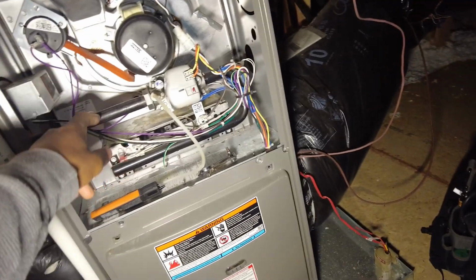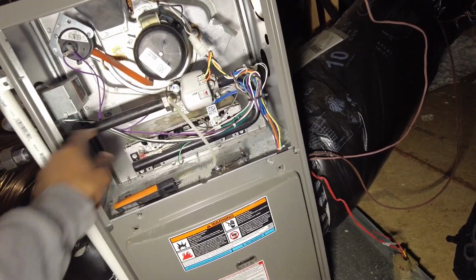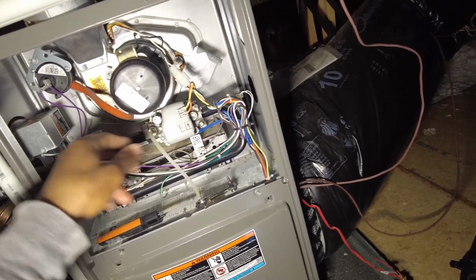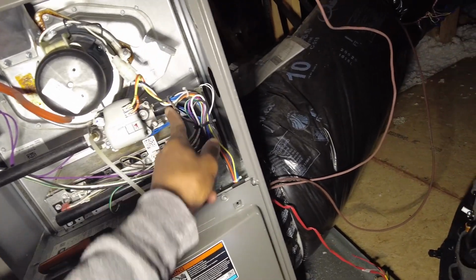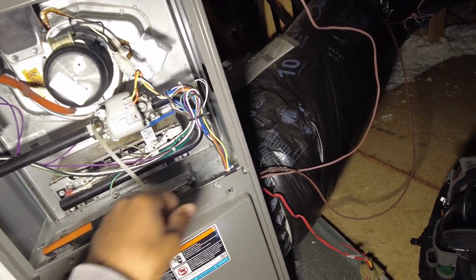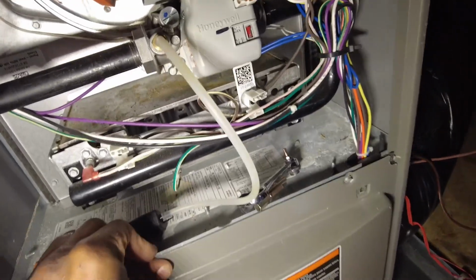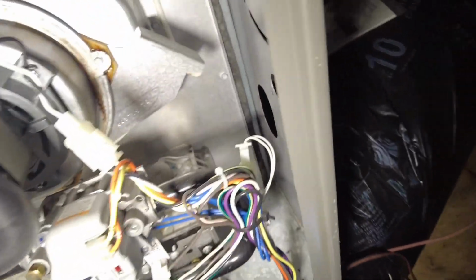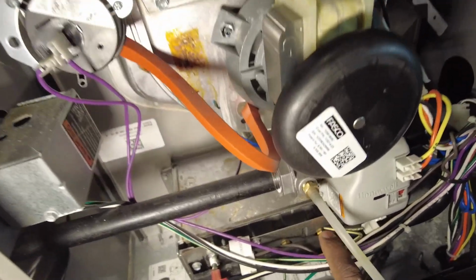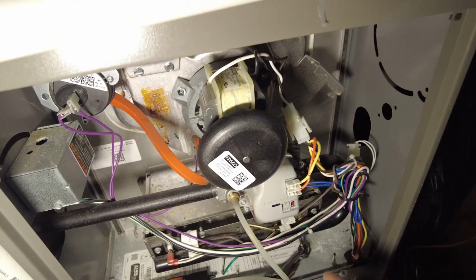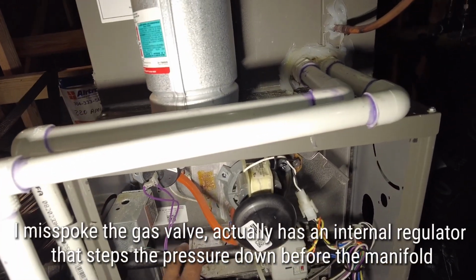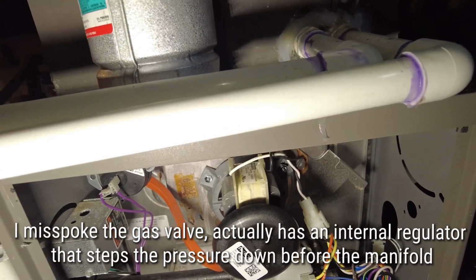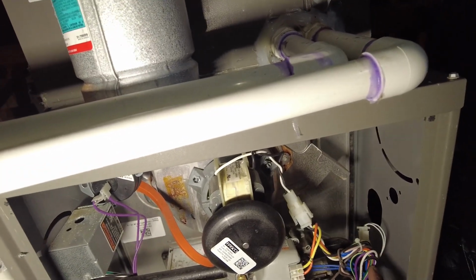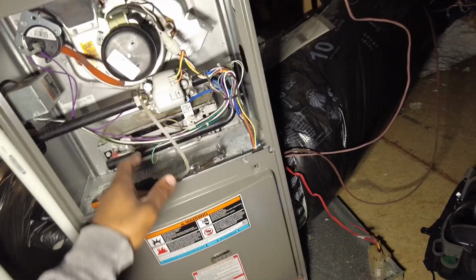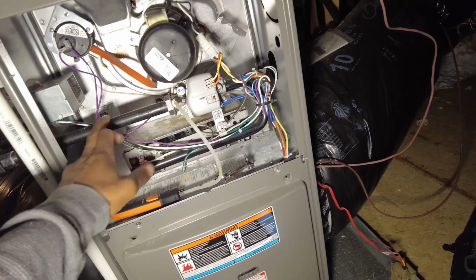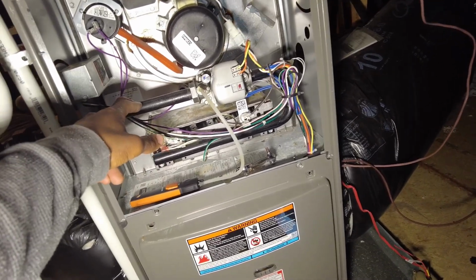This side is going to be the pressure on this line here and back. That makes sense? Mm-hmm. And then this here is showing the pressure that's on this manifold here. Because what happens is there are little orifices on the other side of this. You can't really see it now. Well, you can see it if you looked above and over it. And there are small little tiny brass pieces here, you see? Yeah. So there are small holes creating, because the gas isn't able to flow at the same rate as it's able to flow in here, wide open, these restrictions are creating a back pressure on this line. So it's a little bit of pressure in here. Usually you want that pressure to be between 3.2 and 3.8 inches of water column. In this line you want to be between maybe 5 and 11 inches of water column.